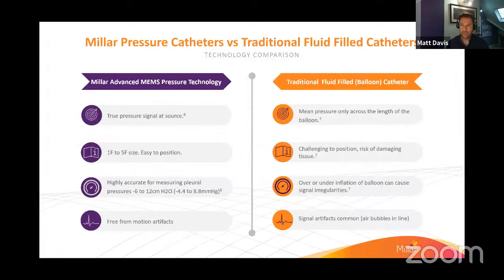When comparing Millar technology to traditional fluid-filled or, say, balloon pressure catheters, a number of differences are clearly seen. I've highlighted a few here on this slide, which include true pressure signal at source. Millar catheters feature the latest sensor-based technology mounted at the distal tip where the pressure measurement is taken. Essentially, you're measuring pressure where the tip of the catheter is placed, as opposed to along a fluid-filled line that connects to an external pressure transducer.